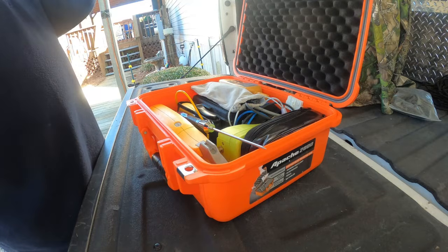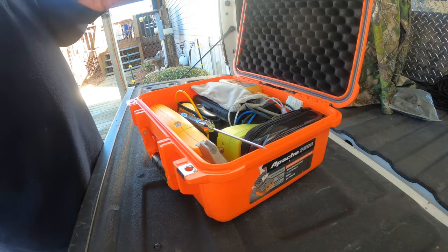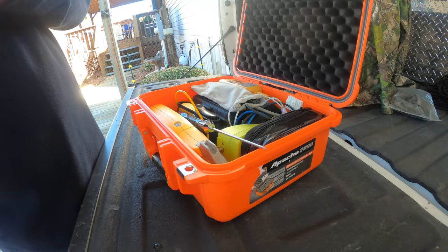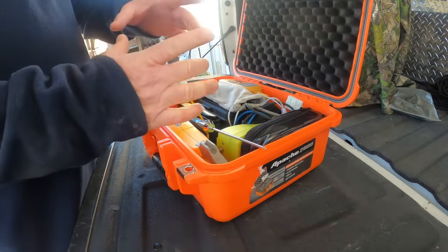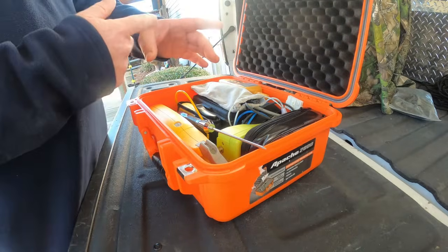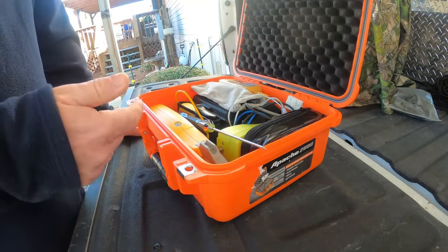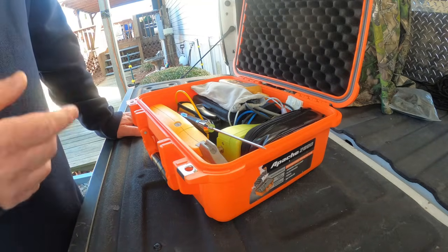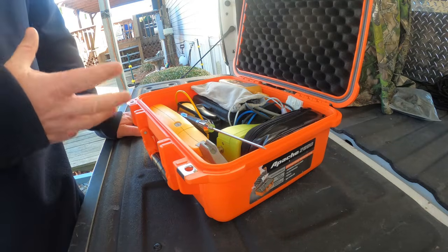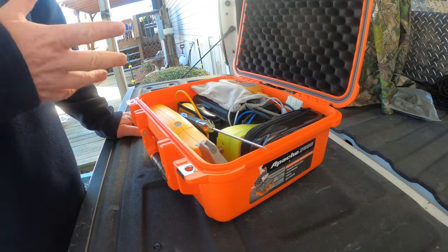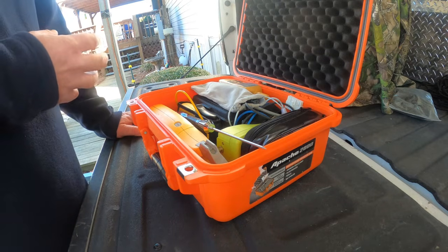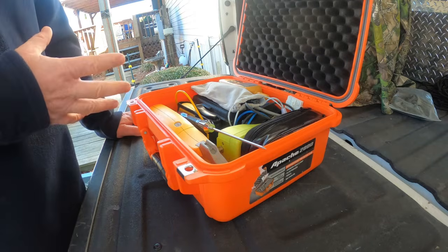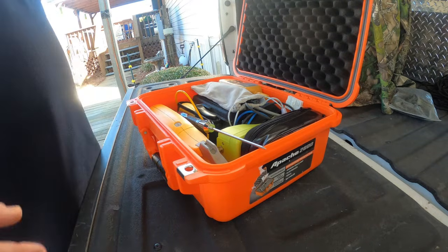Then your other plug will be 1, 2, 3, 4, or 5. They'll be your speed taps and your low voltage control from the unit when you energize G. On some Trane, or the Carrier ICP products actually, will have a circuit board in it that'll have a speed out wire or speed tap wire that will energize that 24 volts over to that motor. Typically you'll see two wires plugged to it if it's not a plug harness. Maybe one's plugged to 2, one's plugged to 4. One's going to be your heat pump or your cooling or your AC airflow. Another one's going to be your heat airflow. So keep that in mind.